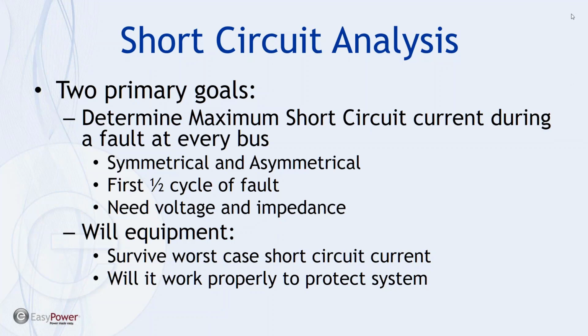Now, the reason for that is, well, what it takes to do that is to have an accurate voltage representation and then somewhere near an accurate impedance summation, and that's where the data collection comes in. So to determine the short circuit current, we need voltage and impedance.